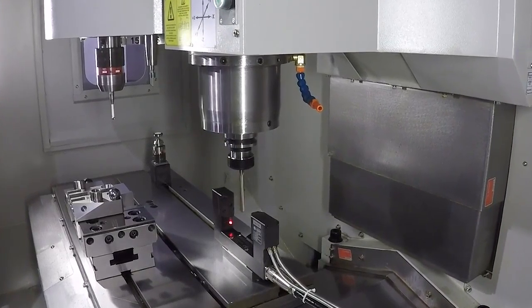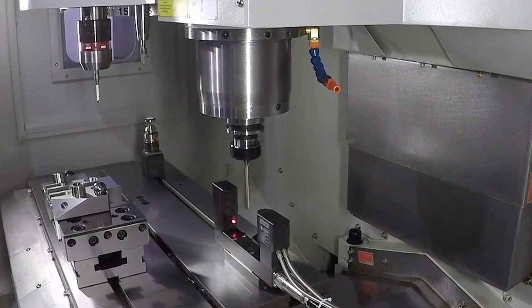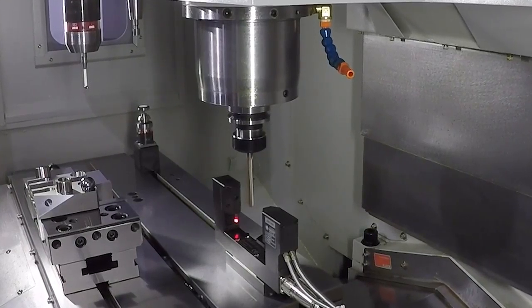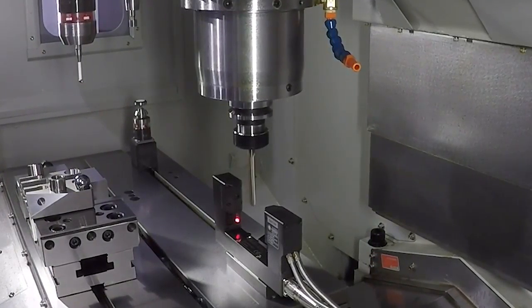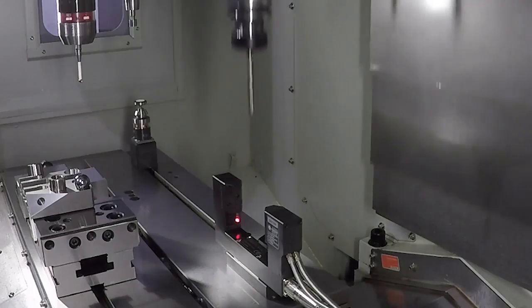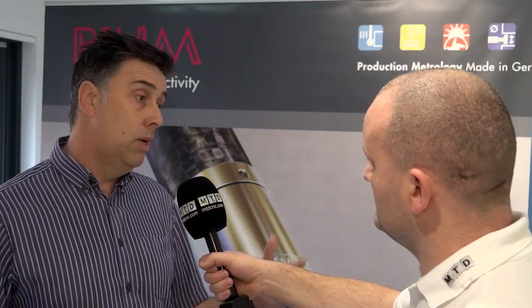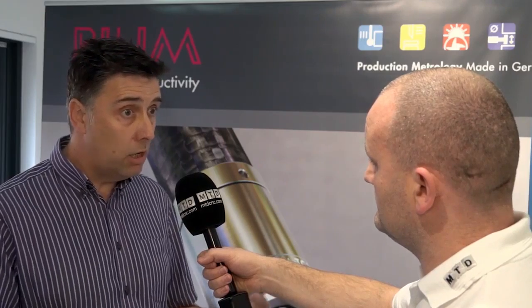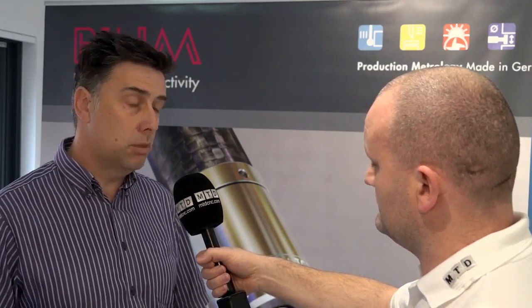Now, as far as we're aware, the competition are doing it by just blowing air across the front of the laser. One, you have the issue of the air consumption that is being used on the system, but also it just doesn't keep the optics clean enough, so you have to go in and manually start to, as part of a preventative maintenance, clean the optics. With the Blum system, you don't have to touch it at all. The shutter system completely protects it from the outside world.